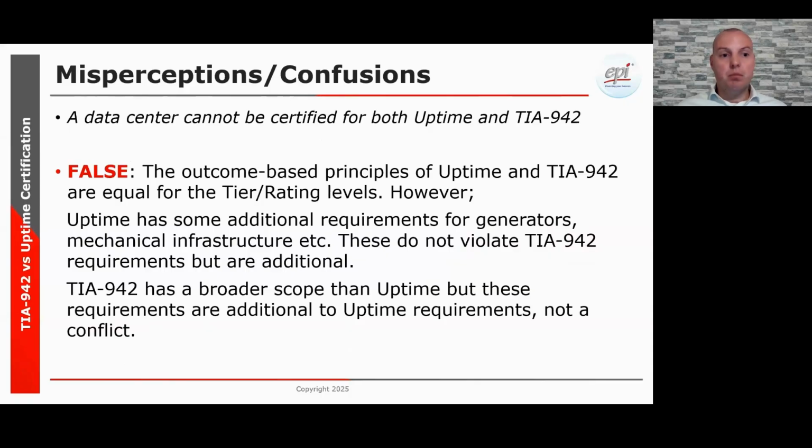The last myth that I want to address is that a data center cannot be certified for both Uptime and TIA-942. This is false. The outcome-based principles for Uptime and TIA-942 are equal for rated or tier levels. However, Uptime has some additional requirements for generators, mechanical infrastructures, and a few more. But these do not violate the requirements and are additional to the TIA-942.